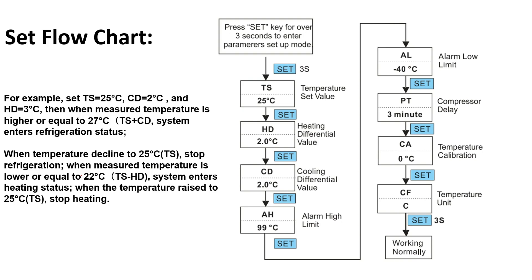When the temperature goes lower than or equal to 22°C — which is the temperature set value minus the heating differential HD — the system enters heating mode. When the temperature rises back to 25°C, the controller stops heating. This is how the controller controls the temperature of your application. PT is the preset compressor delay — if the compressor turns on and off frequently it may get damaged, so a compressor delay can be added to protect it.